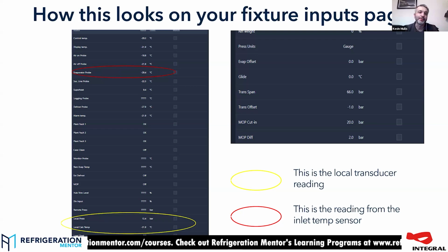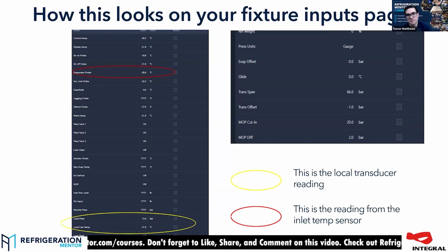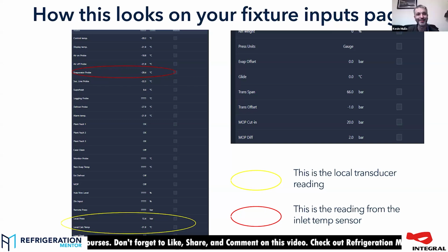The flip side of doing it that way is to tell the controller to open the valve more after a defrost at startup, or give it longer. The problem with doing that: you tell it, when you start up, open the valve 100%. If you've got an iced up coil, regardless of what the superheat is, it's going to ignore the superheat while it's in startup because it has to get the coil going. If you tell it go 100% and you've got an iced up coil, that is a lot of liquid that's going to come back to your rack, whatever that sensor's reading. So there are pitfalls to doing it both ways.